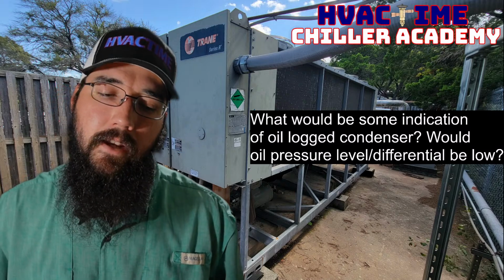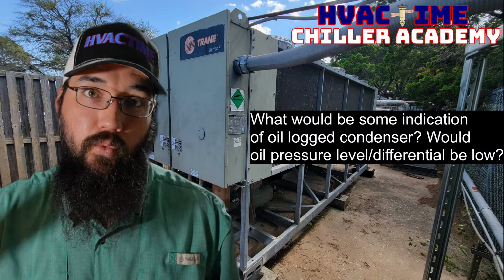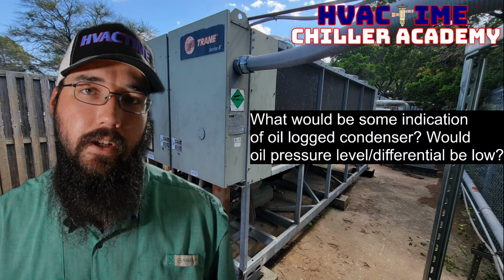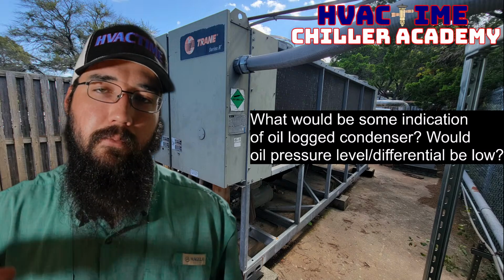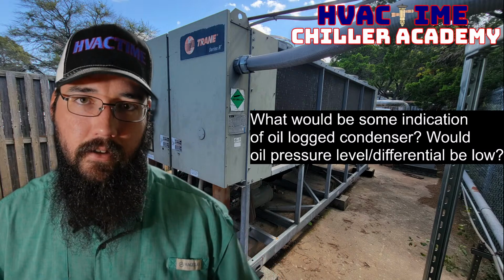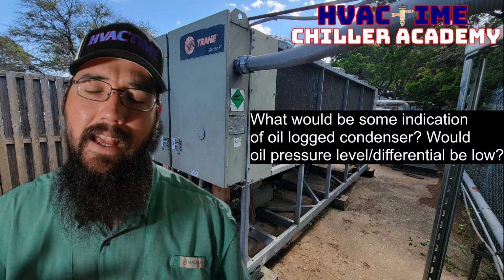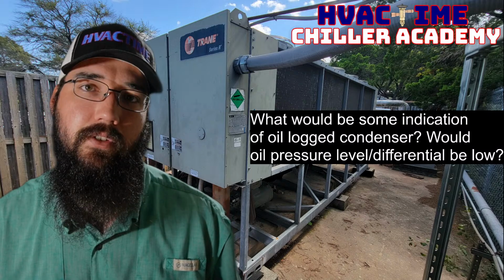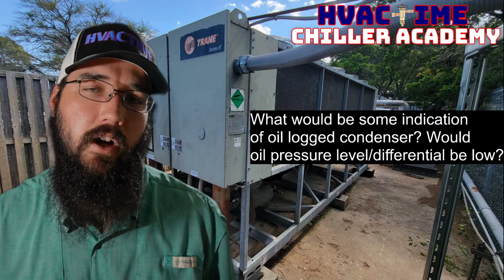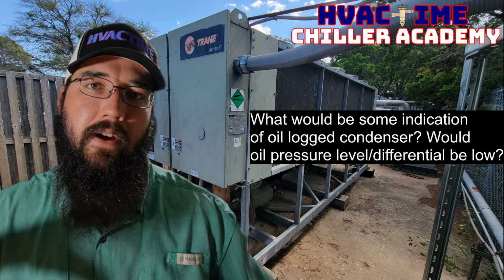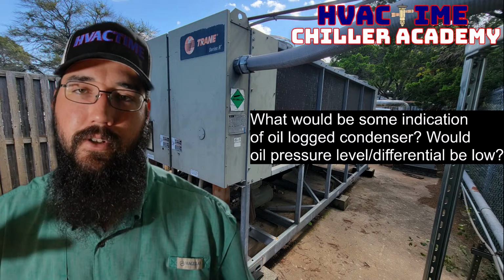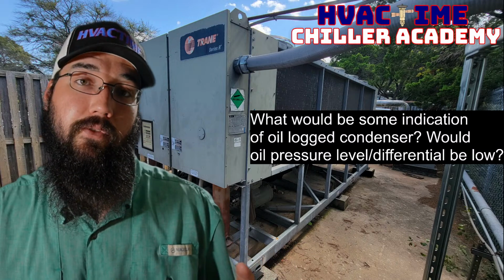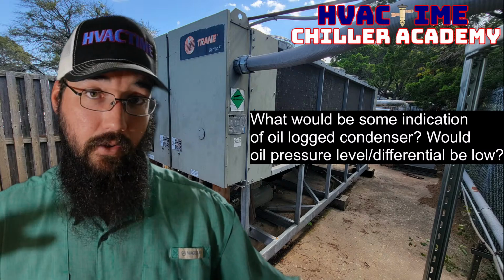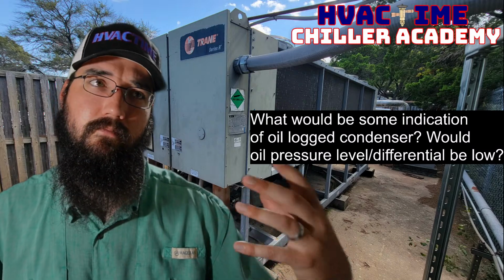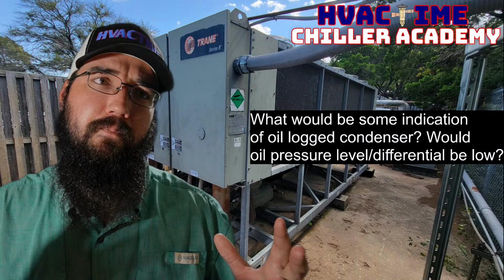Okay? Now, there are scenarios where you have a really unloaded machine, with compressors heavily unloaded, that can lower the velocity through the system enough to cause a similar problem. But most of the time I find it's actually due to the saturation and the pressure and just the force of the flow going through there, which the pressures have a huge part to play in. So that would be the air-cooled side.